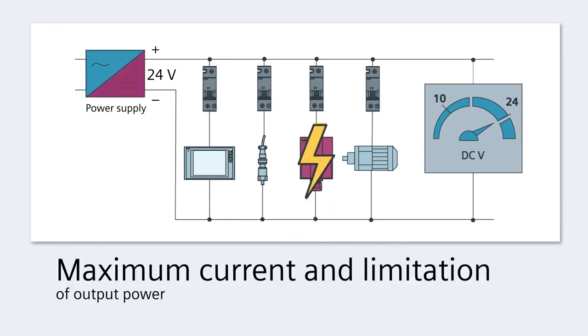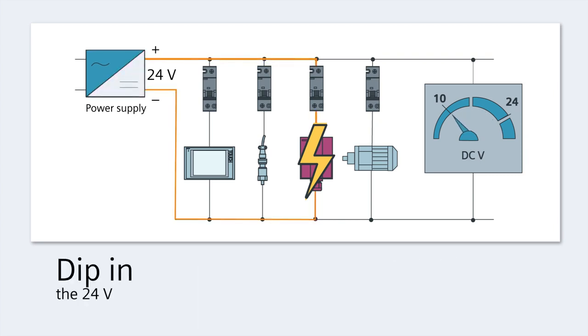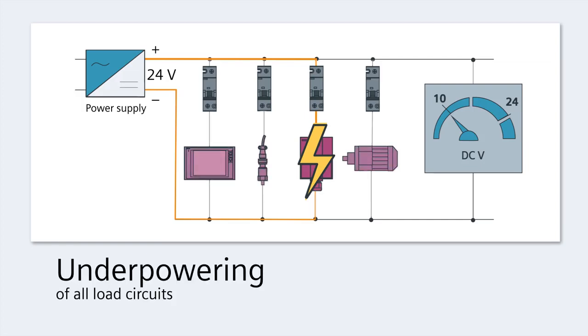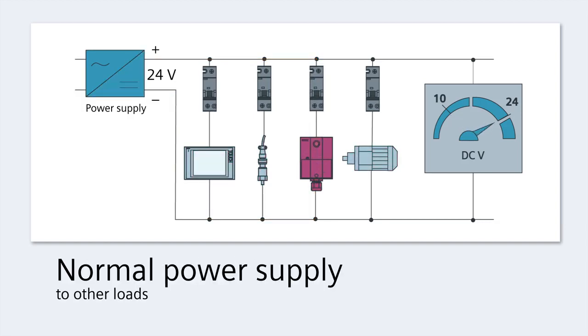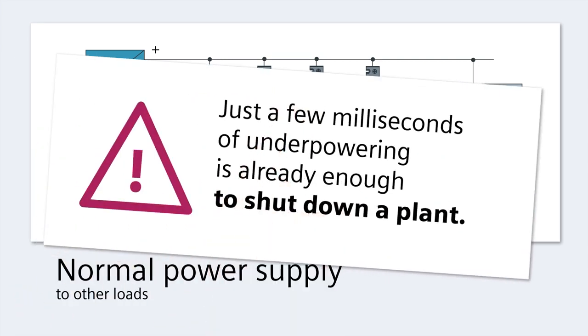The power supply delivers the maximum current and limits the output power. There's a dip in the 24 volts so that all the load circuits are underpowered. But there's often a delay before the miniature circuit breaker trips. This is due to its thermal magnetic tripping characteristic. Just a few milliseconds of underpowering is already enough to shut down a plant.